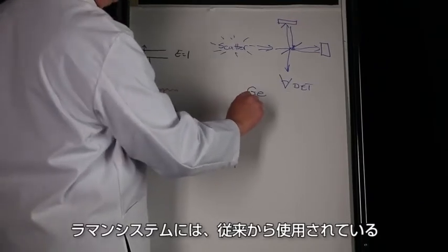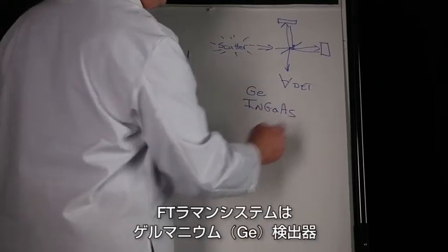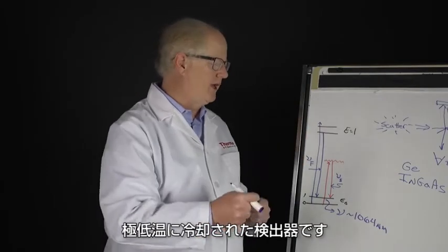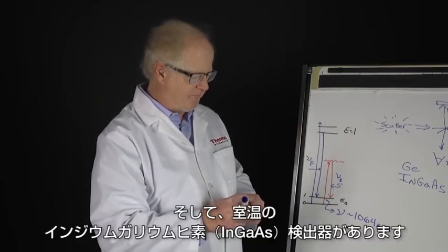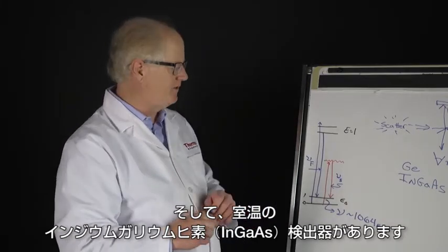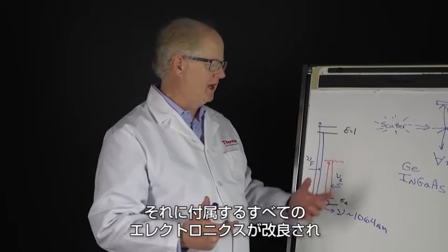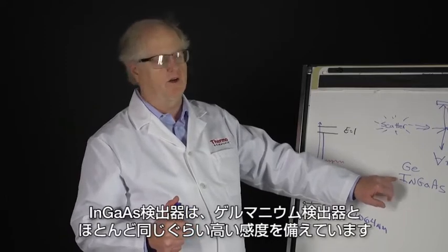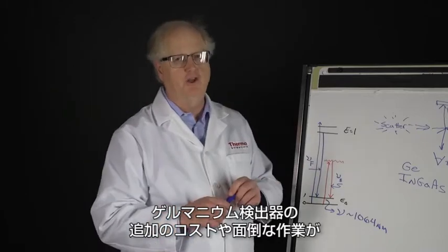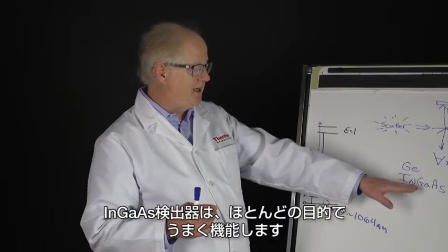The two detectors that have been used traditionally for FT Raman systems are germanium detector with a cryogenically cool detector and the room temperature indium gallium arsenide detector. With the improvement in the preamps and electronics, the InGaAs detector is almost as sensitive as the germanium. There are very few samples for which you need the germanium detector's extra cost and complexity. The InGaAs works just fine for most purposes.